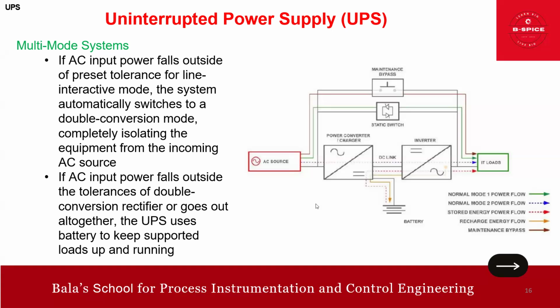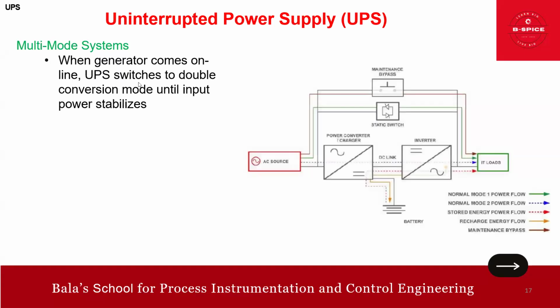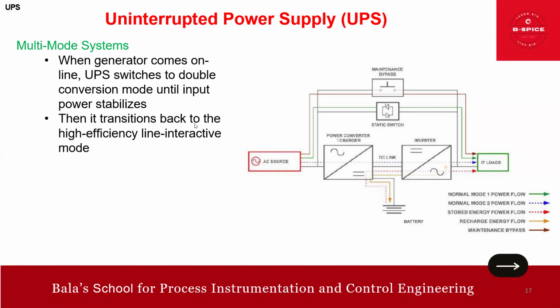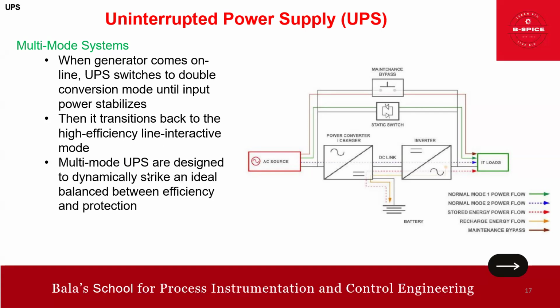Multi-mode is basically a combination of single and double conversion. When the generator comes online, the UPS switches to double conversion mode again until the input power stabilizes, then transitions back to the high efficiency line interactive mode. Multi-mode UPS are generally designed to dynamically strike the ideal balance between efficiency and protection. If you want good efficiency and protection, you can go for this multi-mode system.